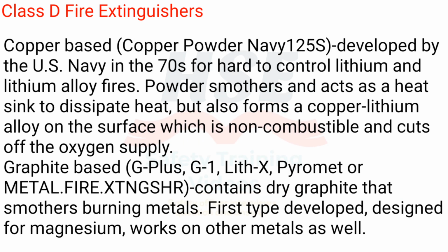Copper-based, copper powder: Navy 125S, developed by the U.S. Navy in the 70s for hard-to-control lithium and lithium alloy fires. Powder smothers and acts as a heat sink to dissipate heat, but also forms a copper-lithium alloy on the surface which is non-combustible and cuts off the oxygen supply.